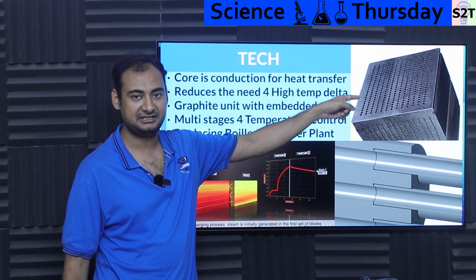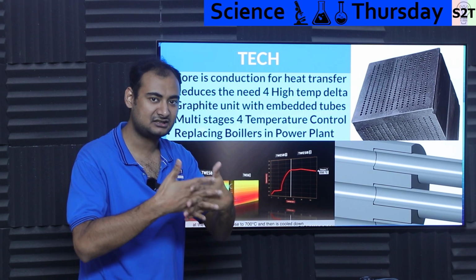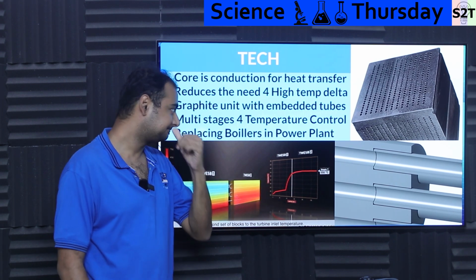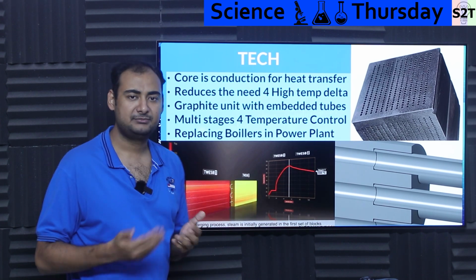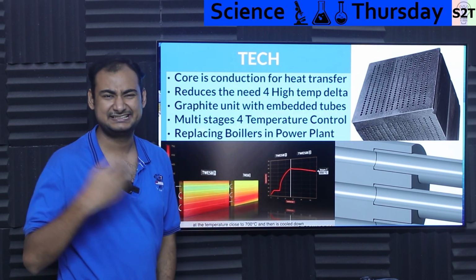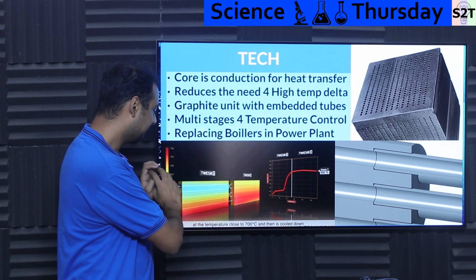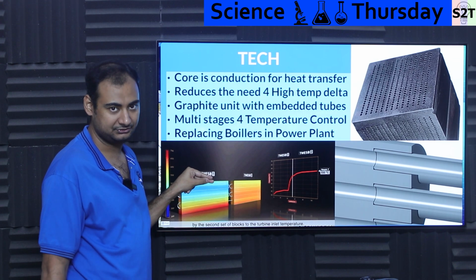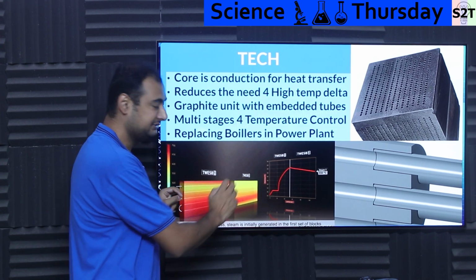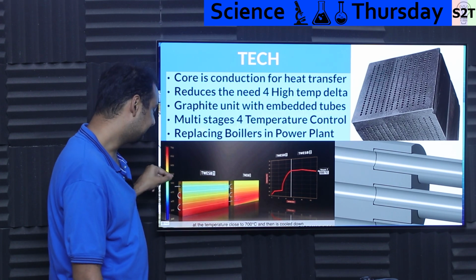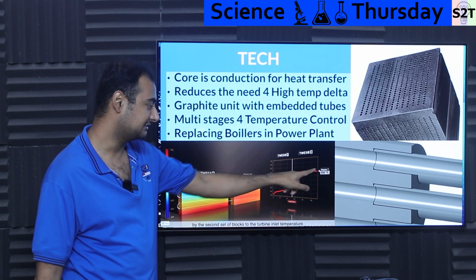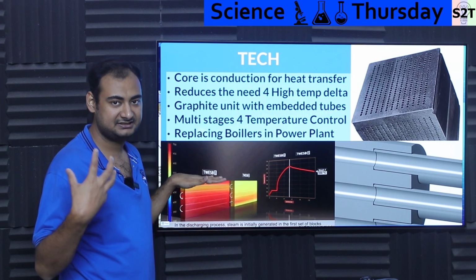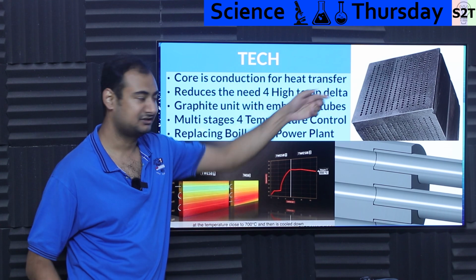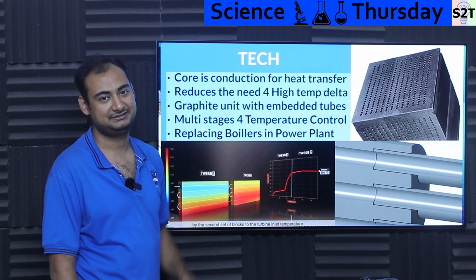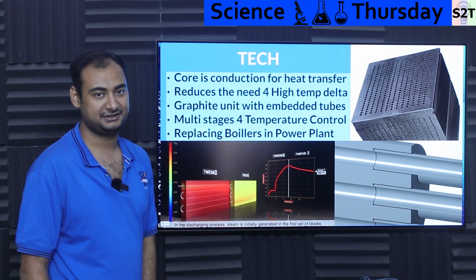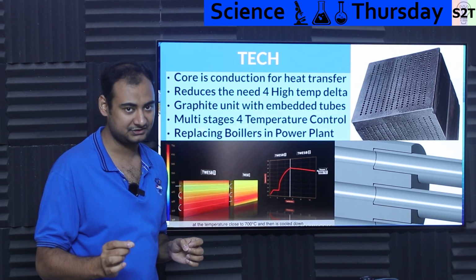So that's a very big advantage. The heaters are physically touching it, the water is physically touching it, so this physical conduction is giving them efficiency. The graphite unit has embedded tubes, and to manage the temperature they are flowing through multiple stages, same as that firebrick company. The idea is, you will get overheated steam if you send it directly through the first unit. So you send it through one unit and then to another, half-depleted unit. So instead of getting 700 degrees Celsius out, you will get 550 degrees Celsius out. As the primary source starts to cool down, the heat starts to flow backwards. That's why conduction is such a critical aspect. And then you still get 500, meaning this can cool down to very little and you still get 500 degrees. Multiple stages allow you to control the output temperature very precisely.